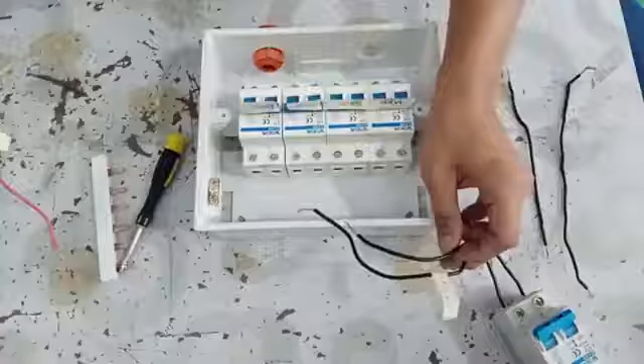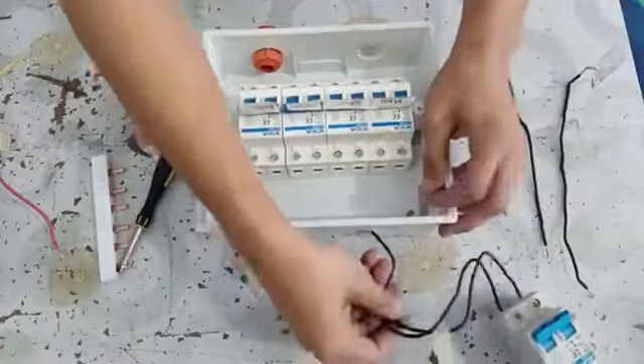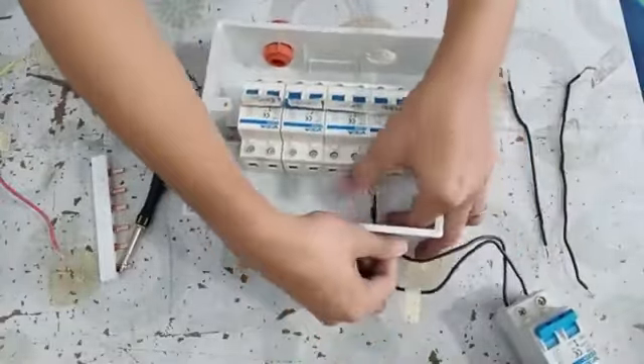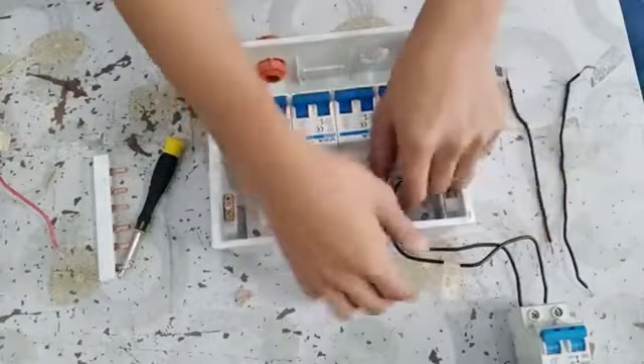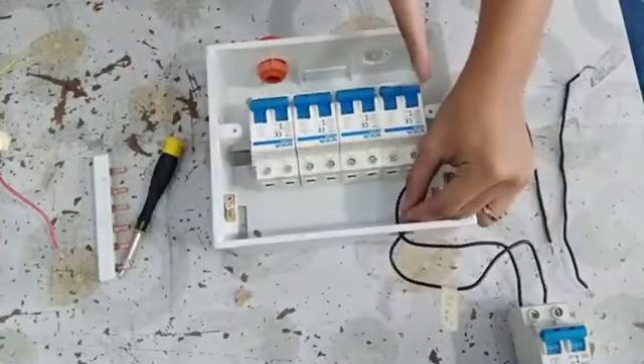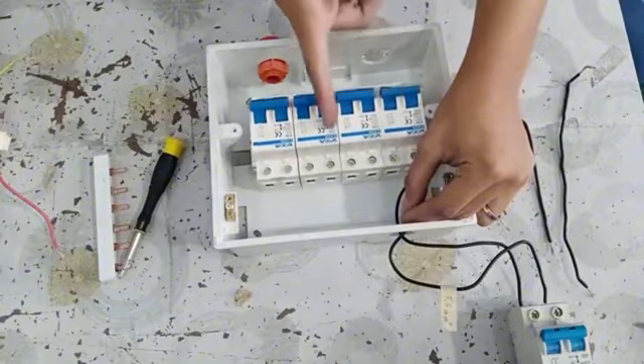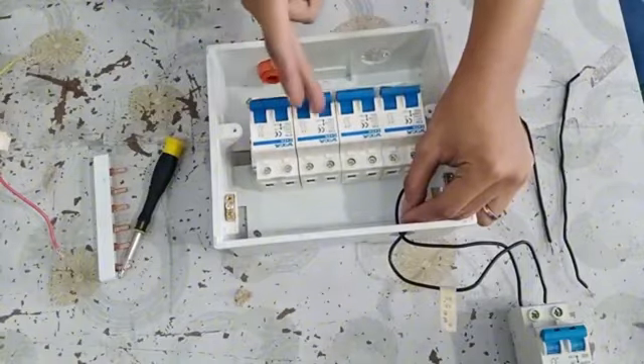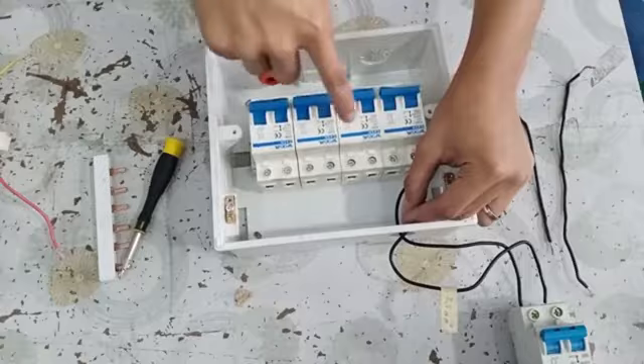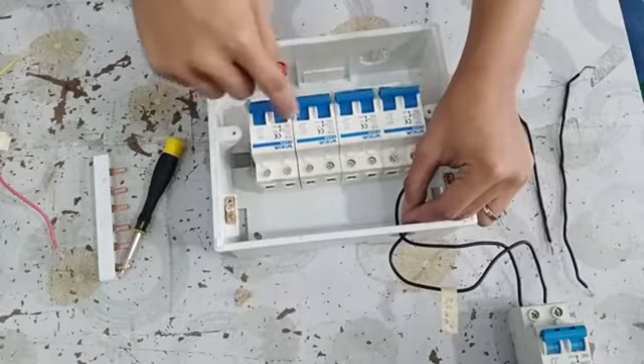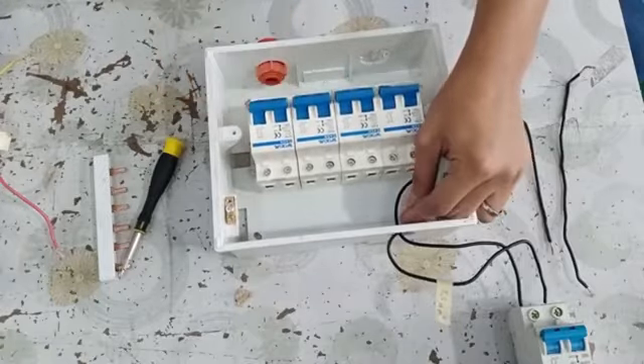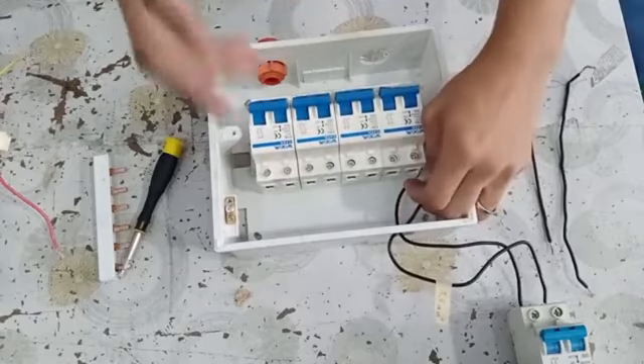When a backstab connection fails, it does not trip the circuit breaker. The breaker only trips on overload or dead short. A high-resistance connection sits below the threshold. Instead, the connection glows. The temperature at the contact point reaches 400 to 600 degrees. You do not see it. It is inside the wall.